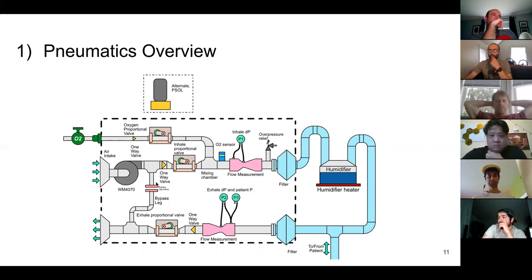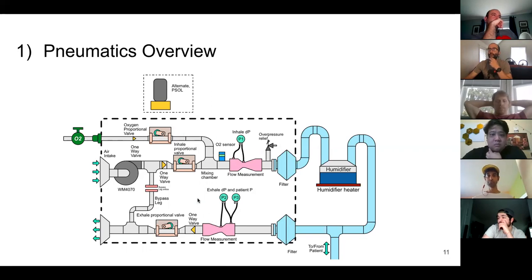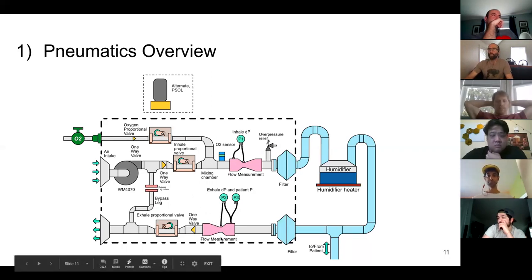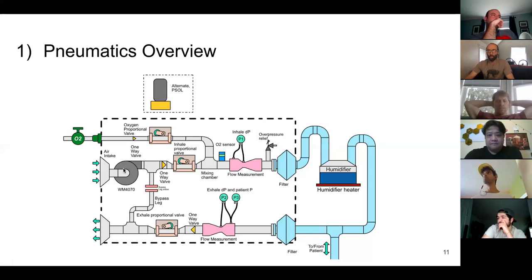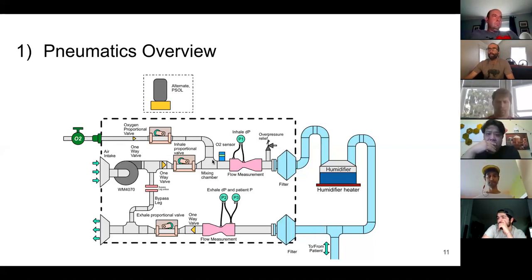That also goes into the mixing chamber. There's this bypass line, which we're still working on the exact implementation. John has been doing some modeling to figure out what resistance that bypass leg needs and which side of the valve it should go on. But that's really there just to protect the fan from its own dynamics and prevent fan surge and fan stall, so that's somewhere between zero and a fairly small amount of flow. From there, those two lines mix, go past the O2 sensor, through the inhale flow measurement, overpressure relief, to the patient.